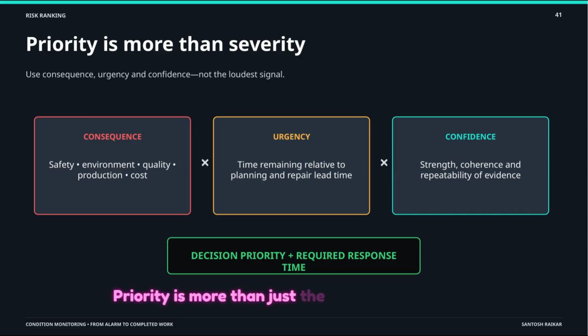Priority is more than just the loudness of a signal. It's a calculation of consequence, urgency, and confidence. A loud vibration on a non-critical backup pump might be lower priority than a tiny, subtle change on a critical main turbine. We focus on the risk, not just the noise.